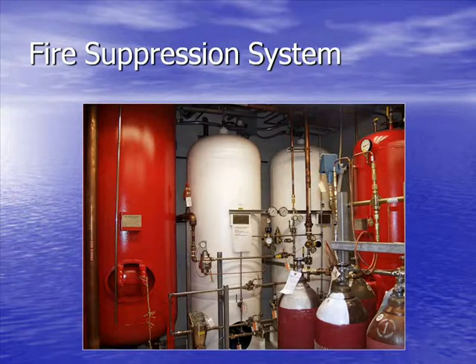Fire suppression is an important part of hyperbaric practice. This is the fire suppression system in the back room. We have two large pressure capacitance vessels — storage vessels for stored air — so if our compressors go down we can do any two dives in and out. The red tanks are the water tanks, which are the deluge and hand-line system for the interior of the chamber.